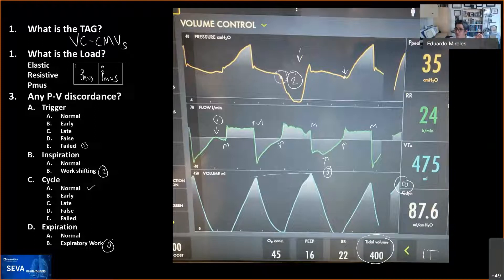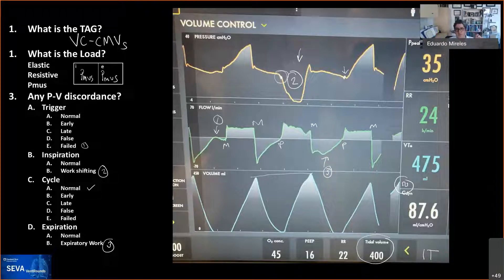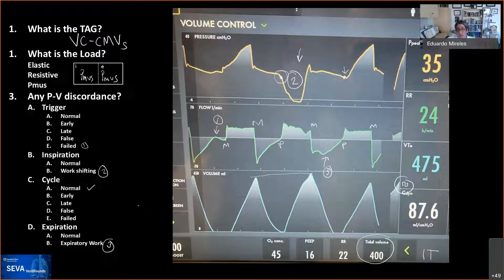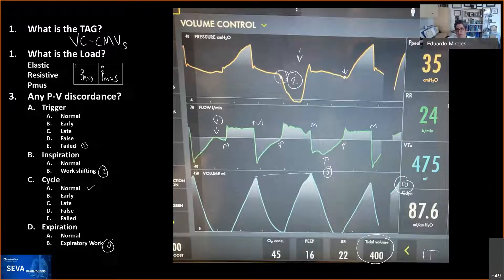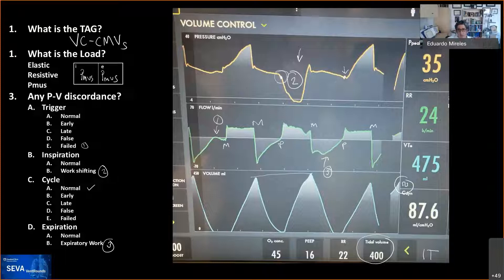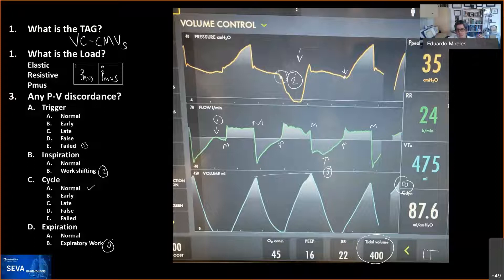Is this flow simulation also on other ventilator models? We don't know — it's the one we recognized because we couldn't read the waveforms and spoke with the engineers. They explained it was related to tube compensation — circuit compensation that all ventilators use to ensure tubing compliance doesn't affect tidal volume delivery. However, the Servo U added this extra feature that modifies the displayed waveform. We're not entirely sure of the clinical rationale for that.